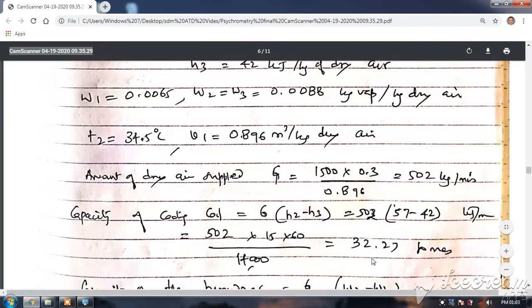Then amount of dry air supplied: m is equal to 1500 people into 0.3 meter cube divided by specific volume, this is 502 kg per minute. Capacity of cooling coil is this m into h2 minus h3, that is 502 into 57 minus 42, so this is 502 into 15 into 60 divided by 14,000, so you will get as directly tons of refrigeration.